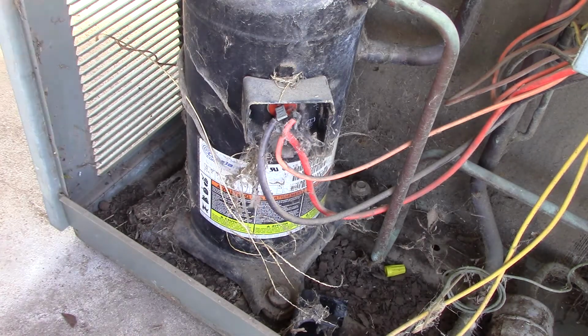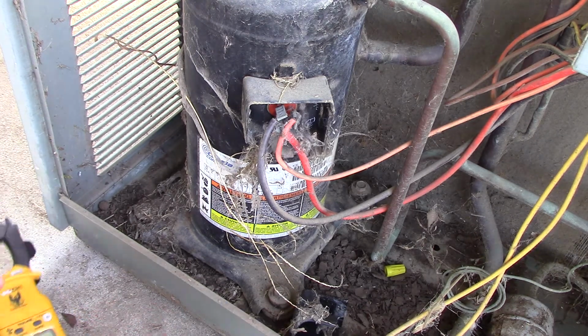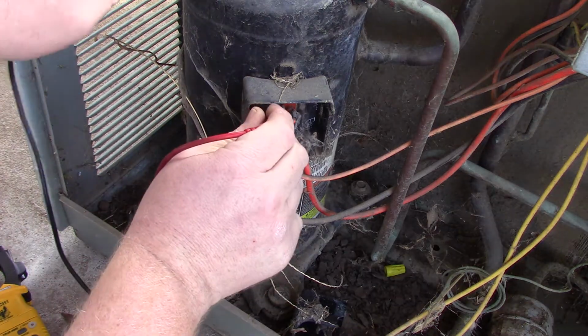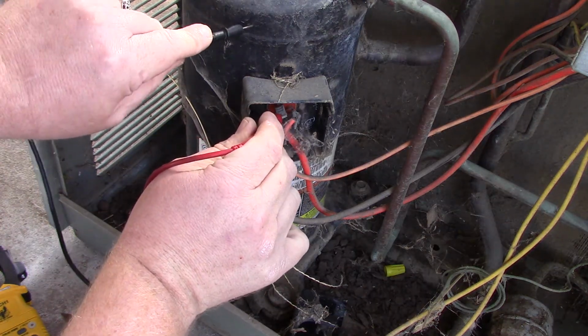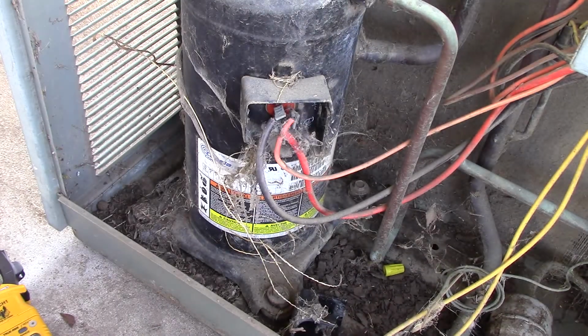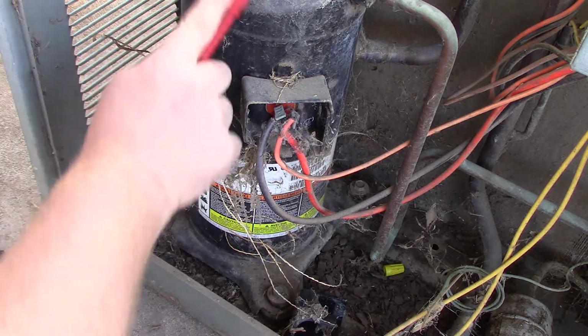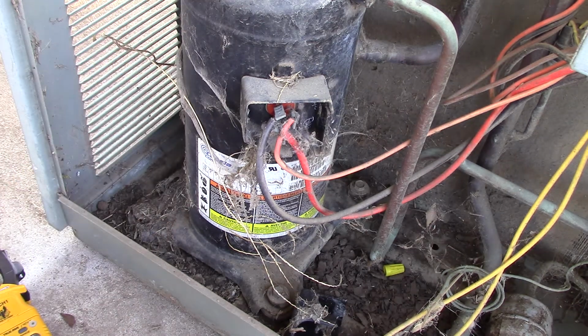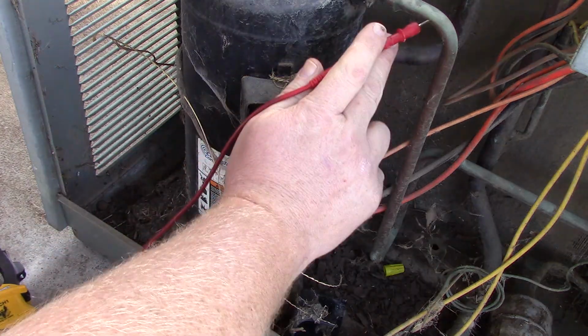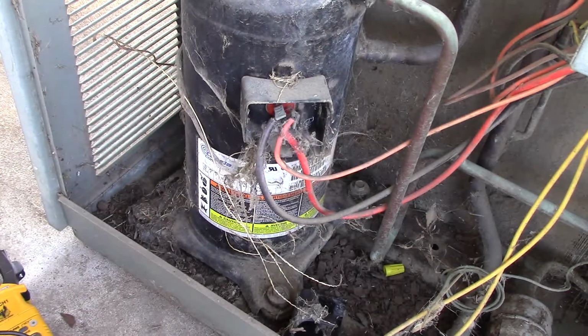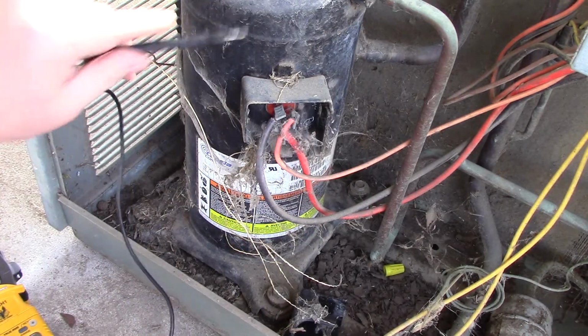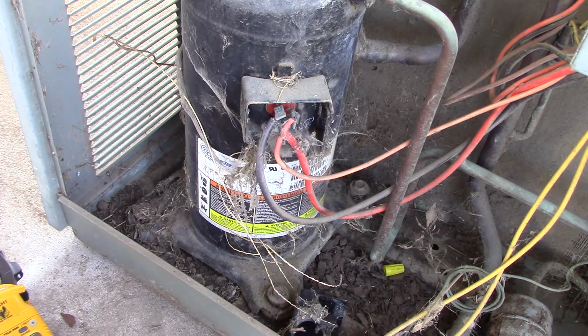Do not, under any circumstances, try to ohm your compressor to ground by going like this and like this. Do not do it here. That black paint creates an insulation. What I've done is I'll take a file, scrape away that paint, then you have bare metal to go to. You can sometimes go to the copper. I prefer just to make a scratch on this enamel on the top to get to the bare metal and go for readings that way.